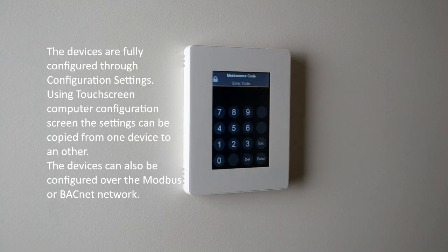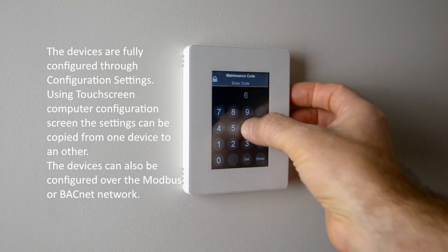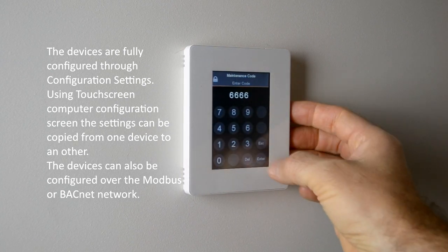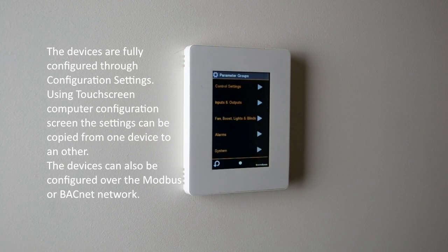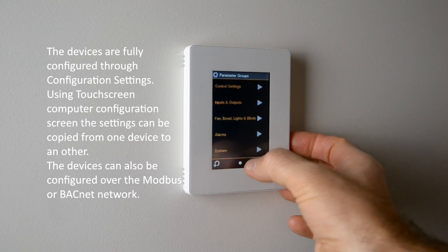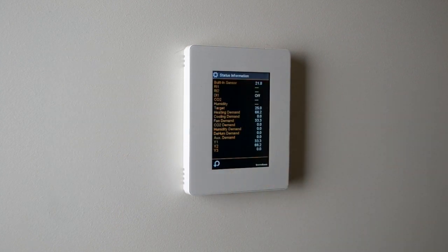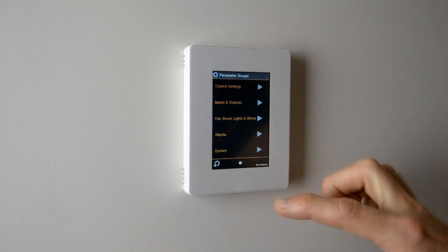So if I press that, it asks for the maintenance code. I need to enter the default maintenance code, 6666, and we go there, and this is now all the configuration settings. Furthermore, we have this little info screen that allows us to see all the readings and outputs for the controller. This is very useful at the commissioning stage to see how the system is operating and evaluating the performance of the system. If I go back, now we have a different menu settings.